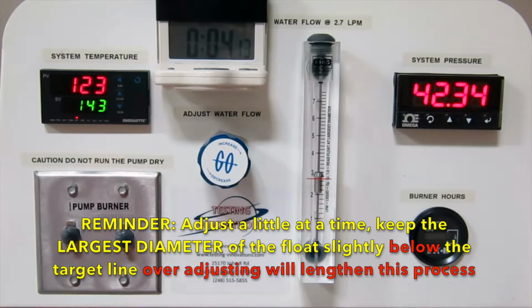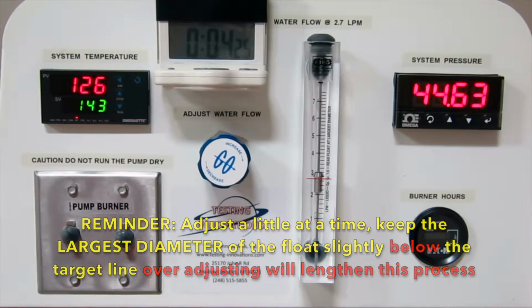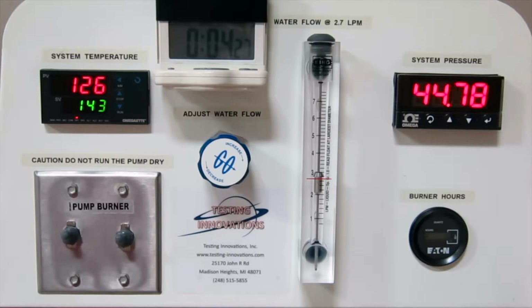Try adjusting a little at a time, keeping the largest diameter of the float just a hair below the 2.7 liters per minute target line on the flow meter. Over-adjusting will turn a 10-minute process into an hour-long process. Once the system has stabilized and the flow has stopped increasing, you can adjust the last little bit of flow to 2.7 liters per minute. This will be at approximately the 8 to 10 minute mark since the burner was turned on.